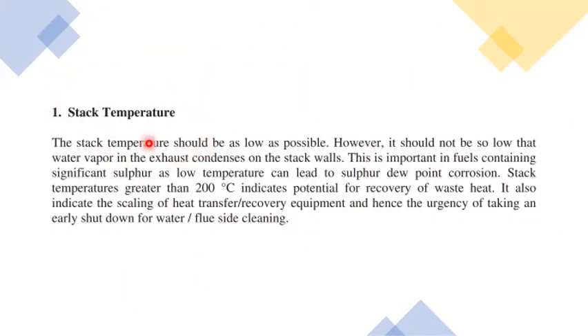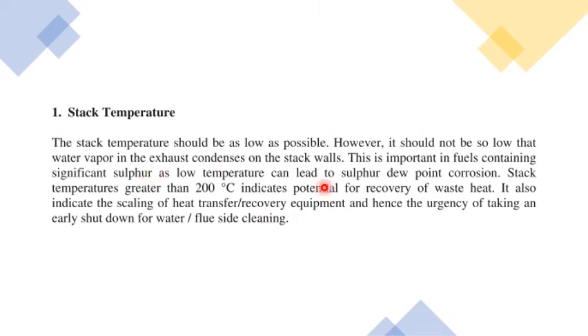The first point is stack temperature. The flue gas coming out of the stack is a very critical area for heat recovery. The stack temperature should be kept as low as possible, but not so low that water vapor in the exhaust condenses on the stack walls. This is especially important in fuels containing significant sulfur, as too low a temperature can lead to sulfur dew point corrosion.